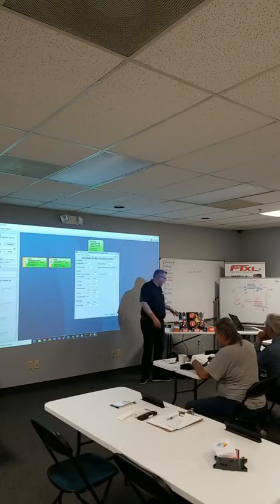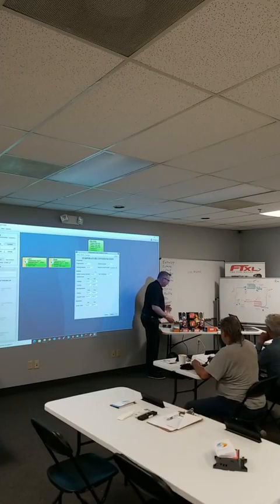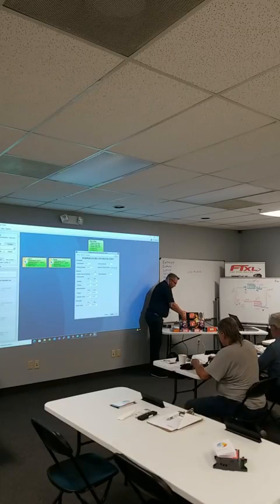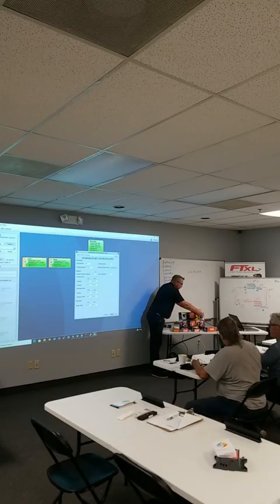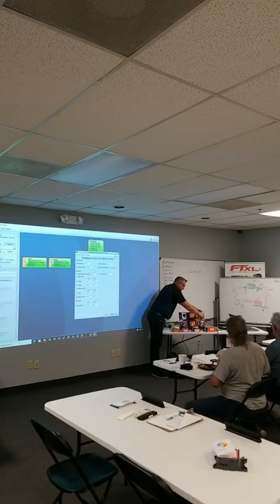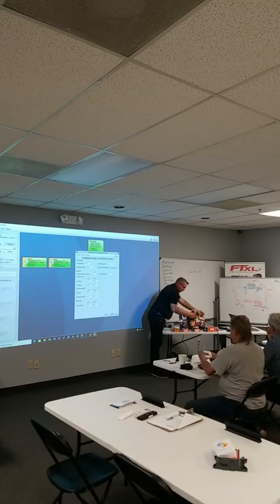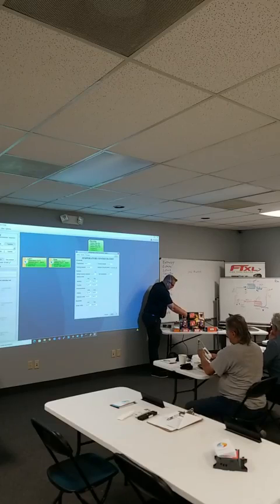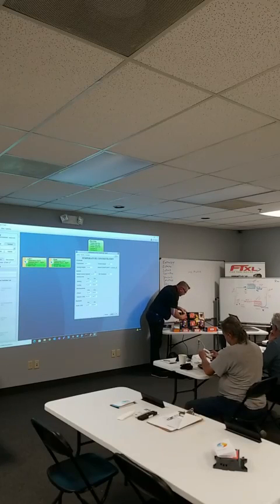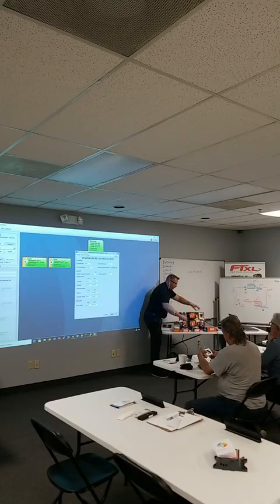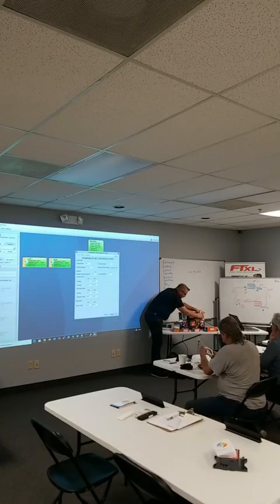Even if I were to swap - and something else to know while I'm doing this - our T1000 has a mode called visualization mode, and what it allows you to do is use it as a commissioning device or a troubleshooting device. Because these communicate, I can take that one off, move it over, plug this one in here, and it'll still work.